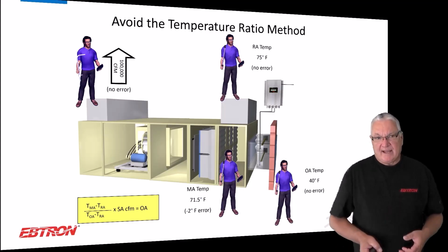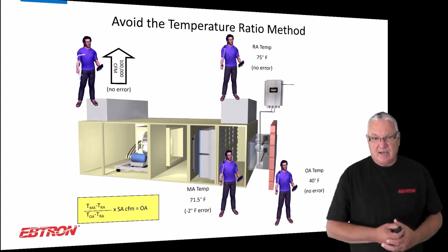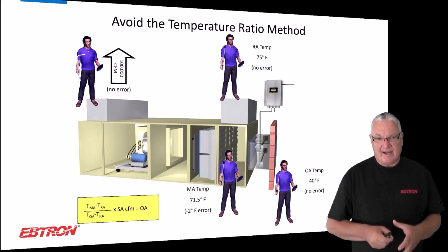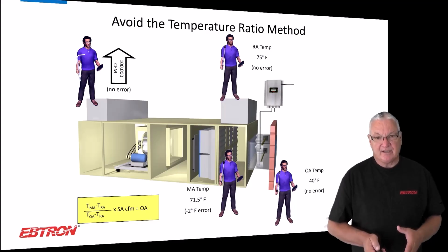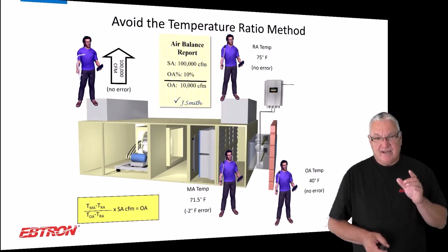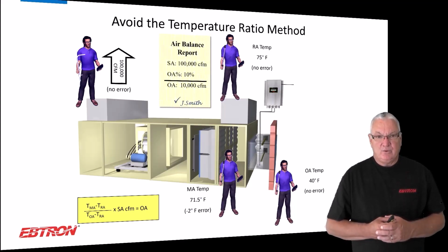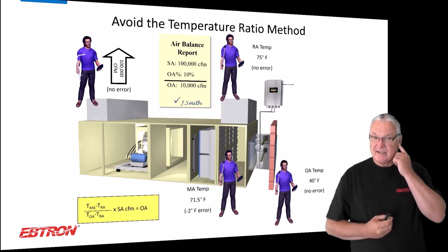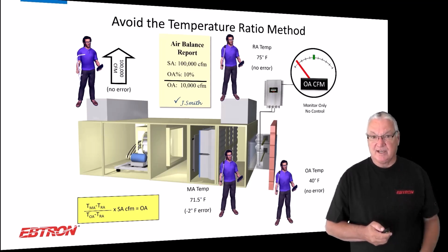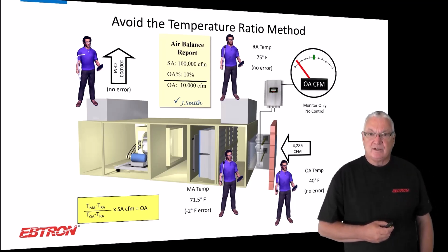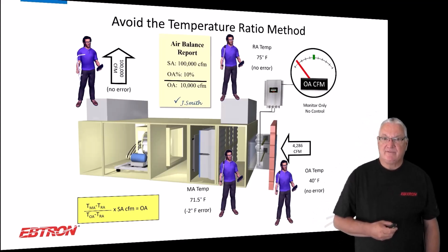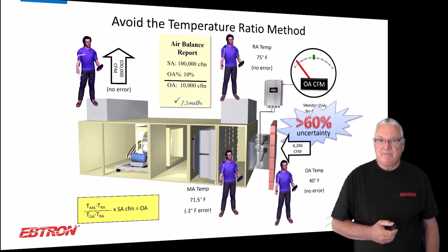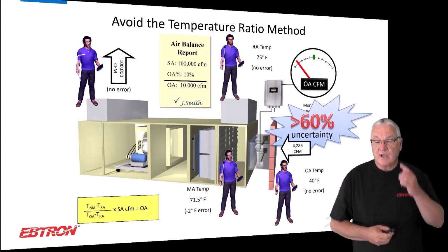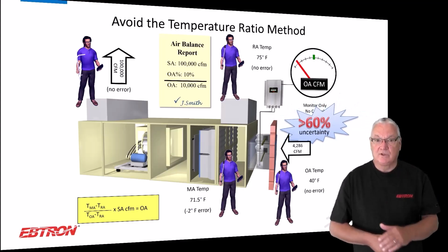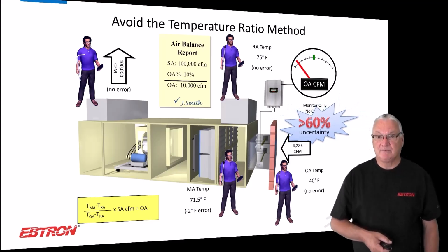If you went back and did these calculations without a bias on the mixed air, meaning you somehow were able to get the actual mixed air temperature, then instead of the 10,000 CFM you would have gotten here, which is 10%, the calculations result in 4,286 CFM. You'd only be 60% off. I don't think that's acceptable, and I hope you don't think that's acceptable.